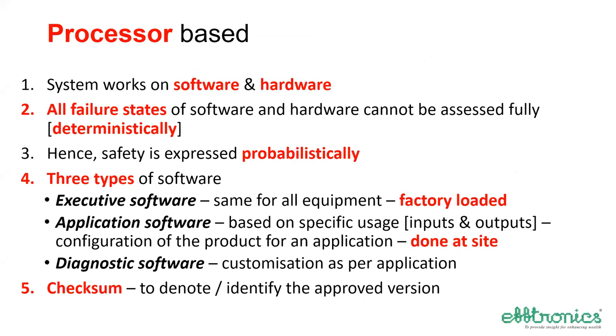And there are 3 types of software. One is executive software, which is the same for all types of equipment. One type of equipment has one software, normally loaded in the factory. Application software is based on where we use that equipment: inputs and outputs, configuration and all that, normally done at site. Diagnostic software, because of the sophistication, is a must, and it gets configured normally along with the application software. To know that the system is working with an authorized version of the software, the checksum is verified by the user or by the people who check it.